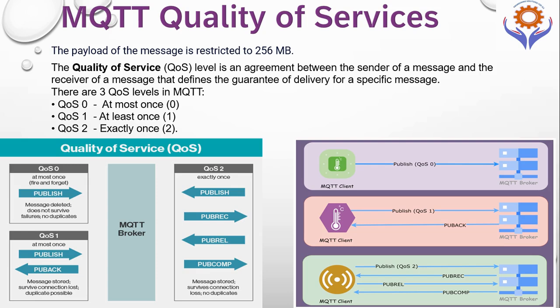For quality of service 1, it gives a guarantee that the message is delivered at least one time to the receiver. The receiver stores the message until it sends back an acknowledgment packet, so you can confirm it has been received. For quality of service 2, it is the highest level of service in MQTT. This level guarantees each message is received exactly once by the intended receiver, with at least two request-and-response flows and a four-step handshake between senders and receivers.